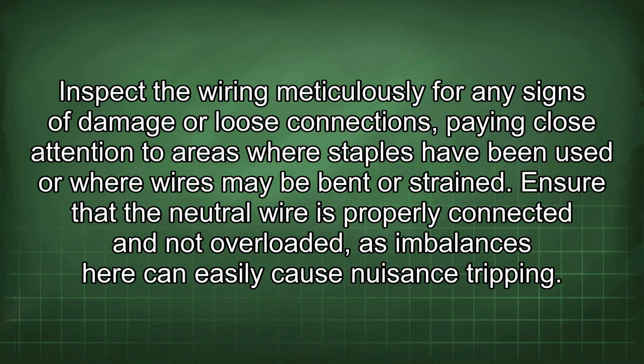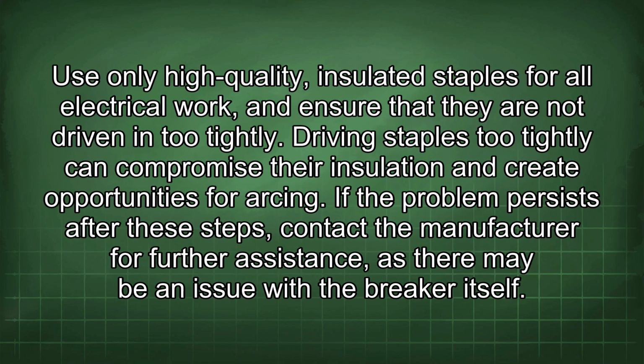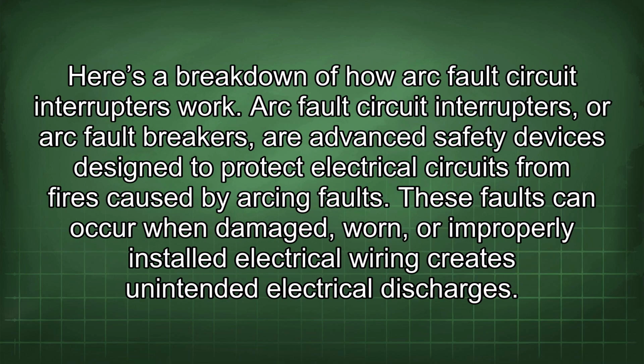Ensure that the neutral wire is properly connected and not overloaded, as imbalances here can easily cause nuisance tripping. Use only high-quality, insulated staples for all electrical work, and ensure that they are not driven in too tightly. Driving staples too tightly can compromise their insulation and create opportunities for arcing. If the problem persists after these steps, contact the manufacturer for further assistance, as there may be an issue with the breaker itself. Here's a breakdown of how arc fault circuit interrupters work.